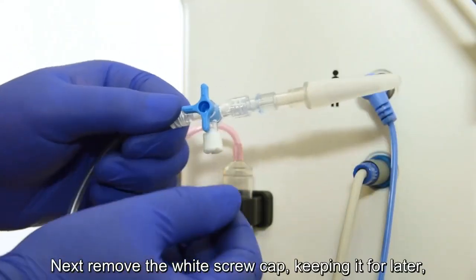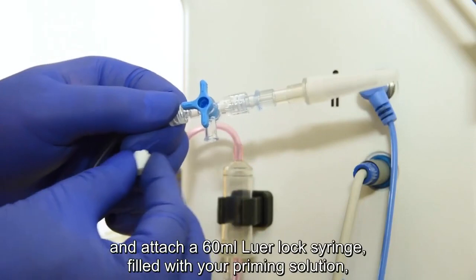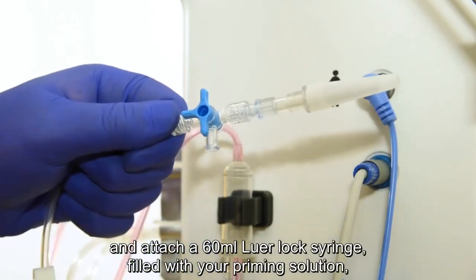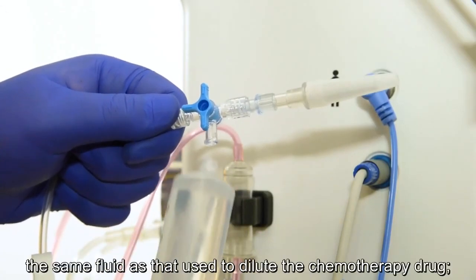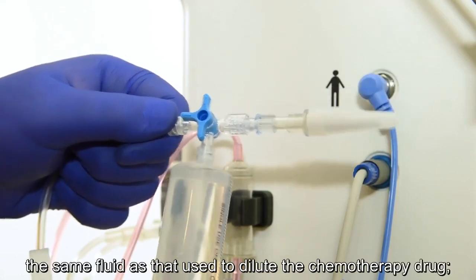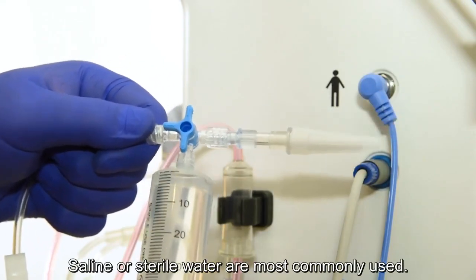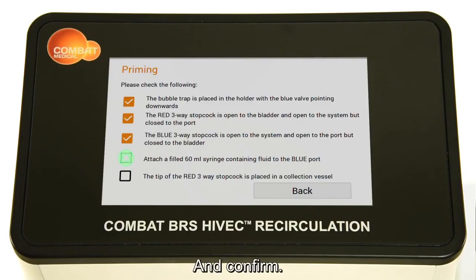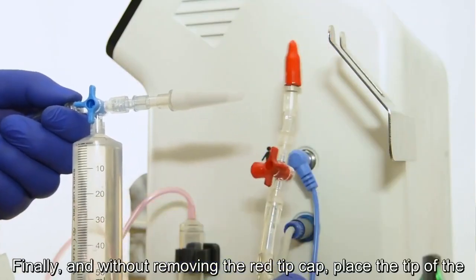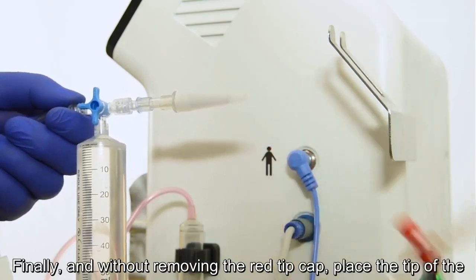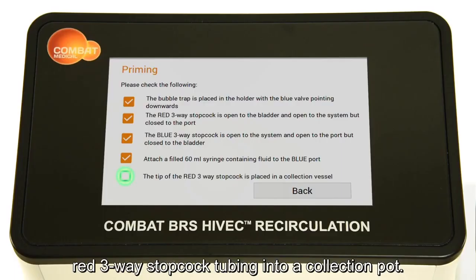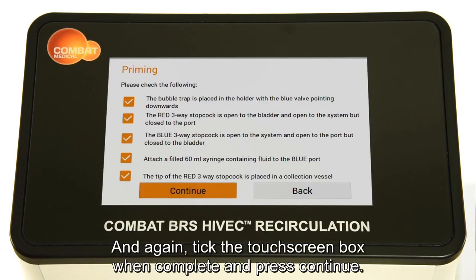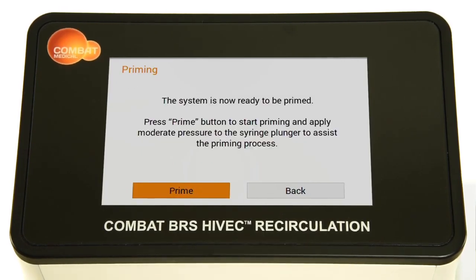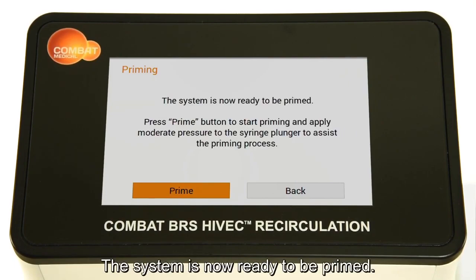Next, remove the white screw cap, keeping it for later, and attach a 60ml Luer-lock syringe filled with your priming solution, the same fluid that is used to dilute the chemotherapy drug. Saline or sterile water are most commonly used, and confirm. Finally, and without removing the red tip cap, place the tip of the red 3-way stopcock tubing into a collection pot, and again tick the touchscreen box when complete and press continue. The system is now ready to be primed.